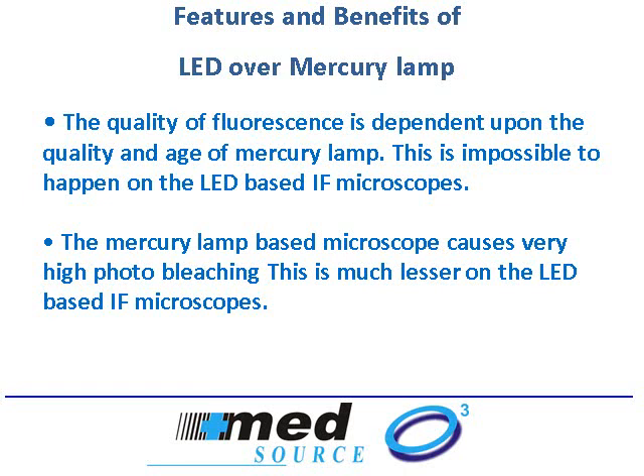Another advantage of Ayrus EPI over mercury lamp based microscopes is the quality. A mercury lamp has a very good intensity at the beginning of the life, so it will be very bright when it's a new lamp, and as the lamp becomes older, the intensity of light reduces. We know this, that in a mercury lamp it is possible that a low positive sample which is reported as positive in a new lamp can be reported as negative on a lamp which is 80-100 hours of use. So therefore the quality of LED which has the same level of fluorescence across the life is much better and people can report more confidently on an LED based microscope Ayrus EPI.